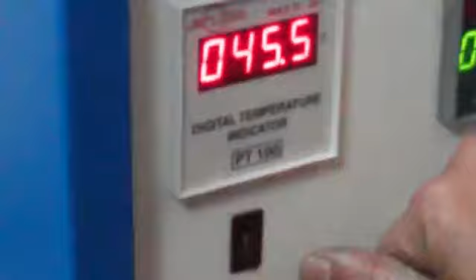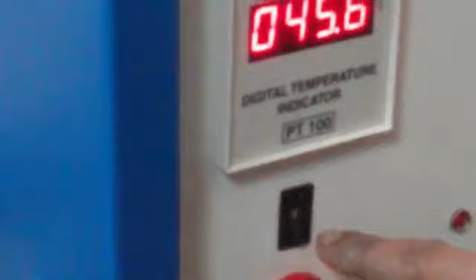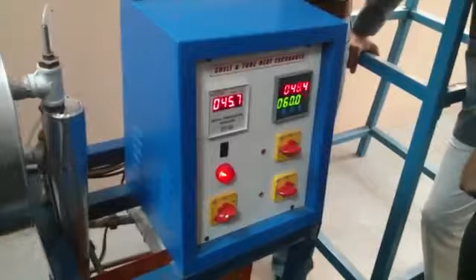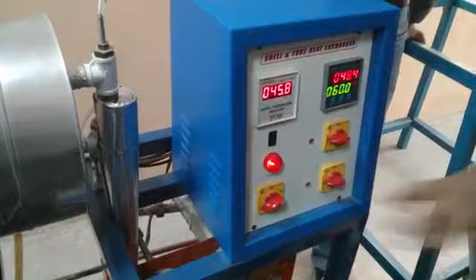So now the hot water flow rate is set, the cold water flow rate is set. Now you need to take the 4 temperatures: hot water inlet and outlet, cold water inlet and outlet. For that, I'm setting one temperature, let's say T1, and waiting for it to become steady. It will take some time, say 5 to 10 or 15 minutes. Once T1 becomes steady, assume all the temperatures have become steady, and we'll take all the other temperature readings.